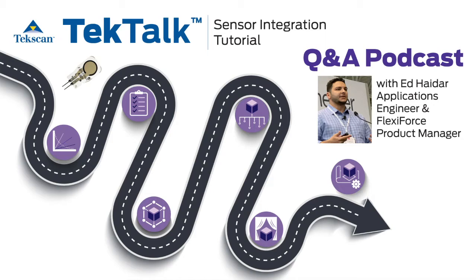What I would first recommend is taking your sensor and characterizing it using the automated loading profile for linearity on the characterization fixture. It's a 5-step linearity test. It's fairly quick to run the profile, and what you'll see is the voltage versus force curve for that sensor under the selected circuit.